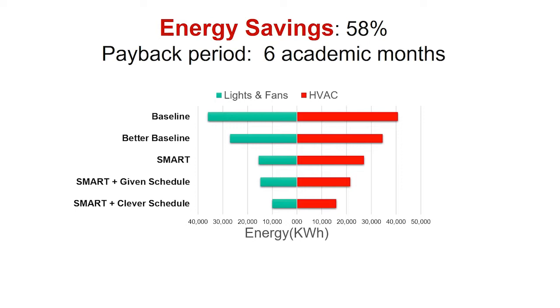All of this put together gives us a fairly large energy saving. This is for lights and fans, this is for HVAC. That is heating, ventilation, and air conditioning. This is a baseline. This is when seven hours continuously the room is occupied. The room is climate controlled and lights and fans are on. It used to be the case. Now, we have better baseline if you turn off the air conditioning and other things during the lunch time. A smart one, which has some of the components of the solution. If you take a given schedule, you get this. And if you get a clever schedule by moving the meetings around, you get something like this. All of this can add up to a savings of 58%. And that is about six academic months of payback time. Very impressive, I think. We have been able to repeat this in other places also, including auditoria and my lab.